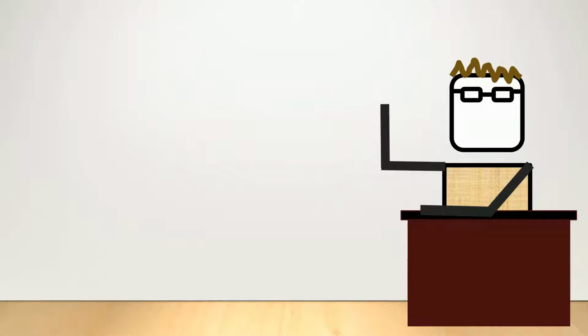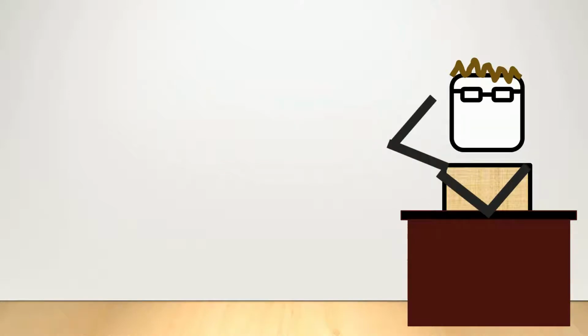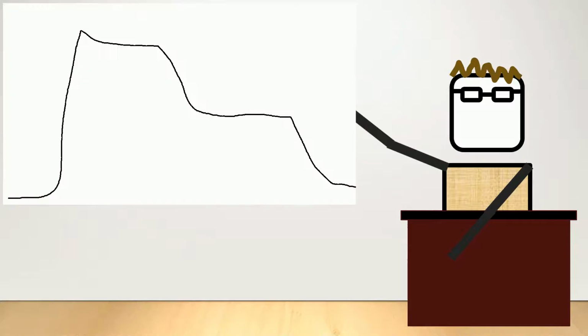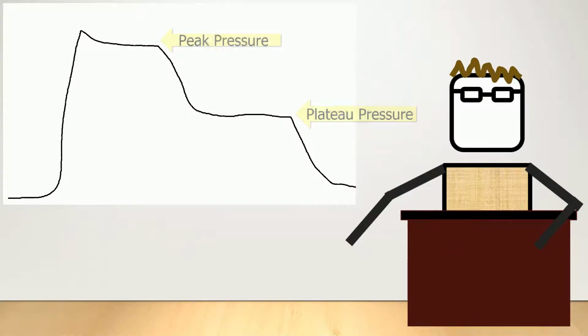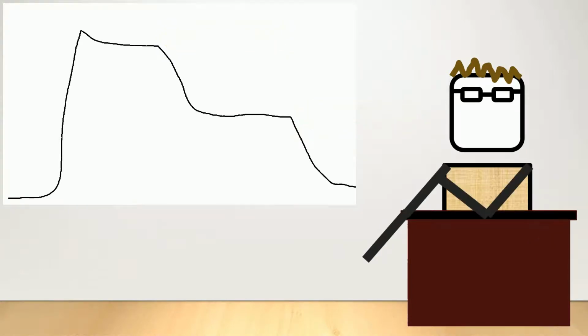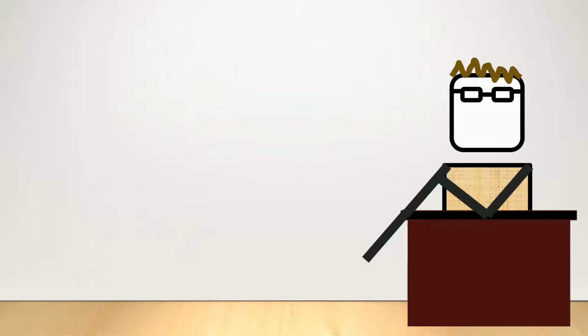If you're still struggling to figure out the cause of the increased pressure and the patient is reasonably stable, then you can consider doing an end inspiratory hold to measure the plateau pressure. As you can see here, if the plateau pressure is lower than the peak, then the increased peak pressure is due to an airway obstruction. On the other hand, if the peak and plateau are close, then the increased peak pressure is due to a change in the lung compliance because the plateau is high as well.